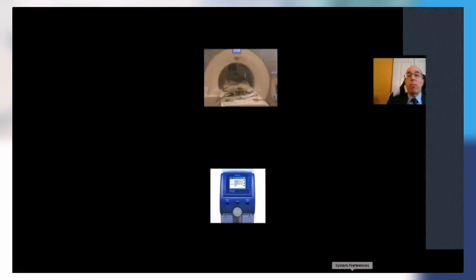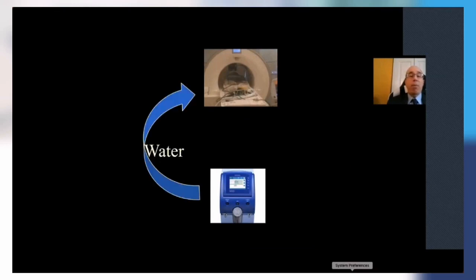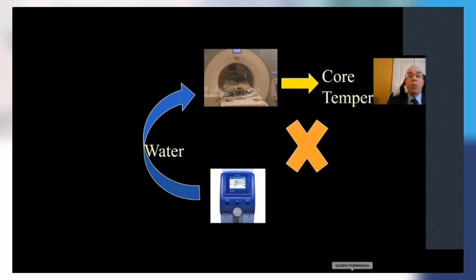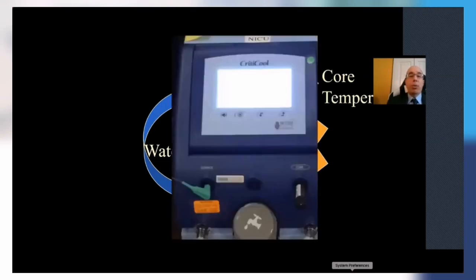Now, with the neonate in the scanner, the surface probe and the rectal probe, which insert into the CritiCool, are not MRI compatible. So in this scenario, we have the water that circulates, and then we have a core temperature probe, which is MR compatible, going to a separate device. That device does not hook into the CritiCool. So what we have to do is manually enter the core temperature. And the way we do that is with the simulator.